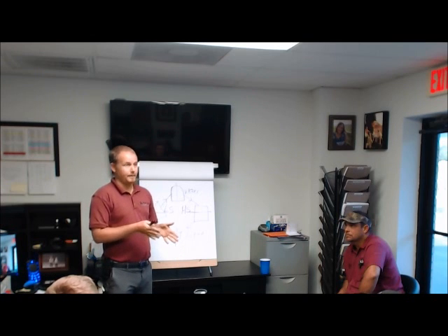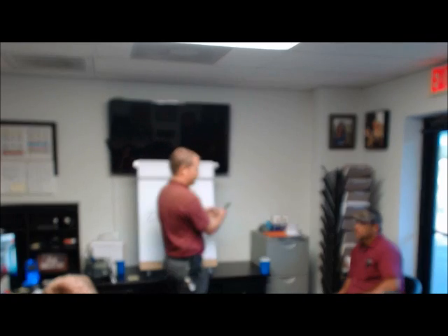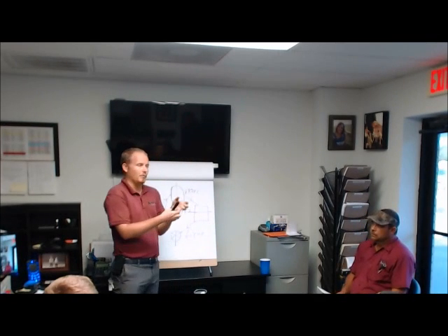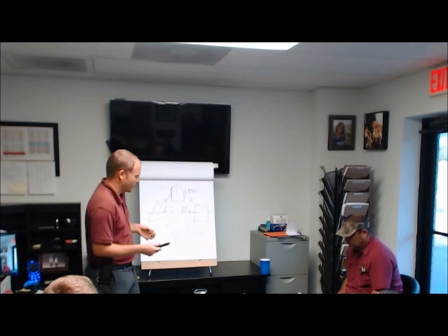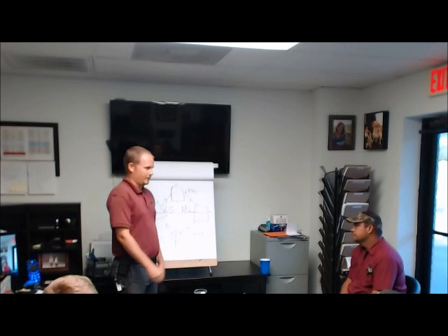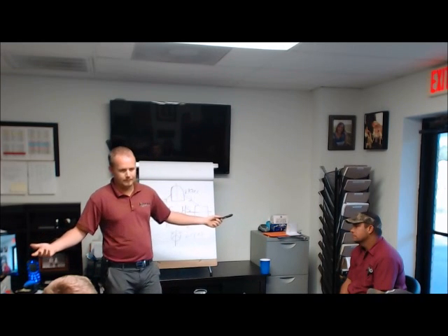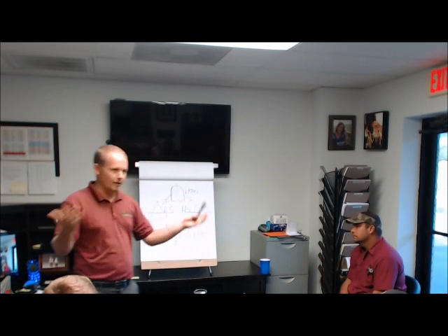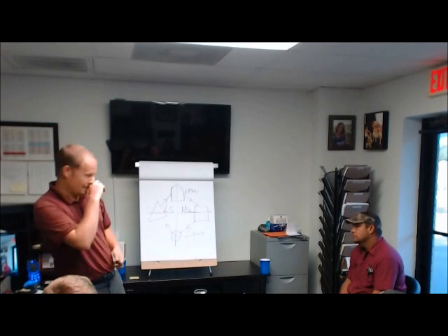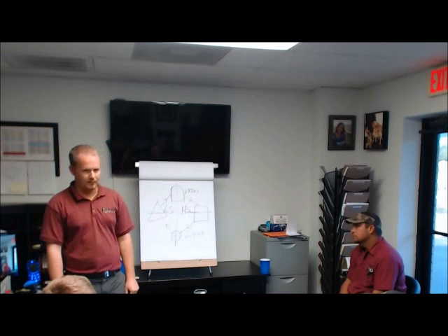Now, when you start to get into actually checking the charge accurately, you have to get a little bit more detailed about what you're supposed to be accomplishing. So, let's say I'm supposed to have liquid here, but I don't have liquid. I have a mixture of liquid and vapor. How am I going to know that? Practically speaking, knowing what we know now, you don't have to give me any specific numbers, but I'm supposed to have liquid here because this is the liquid line, but I don't have liquid in that liquid line. How am I going to know?